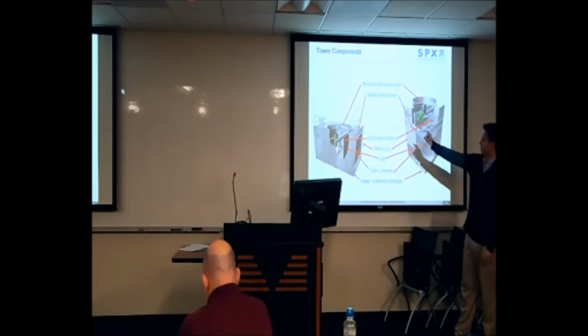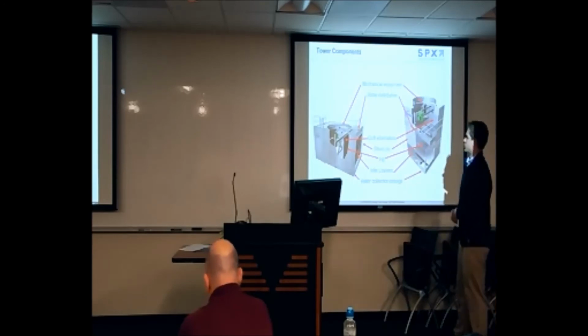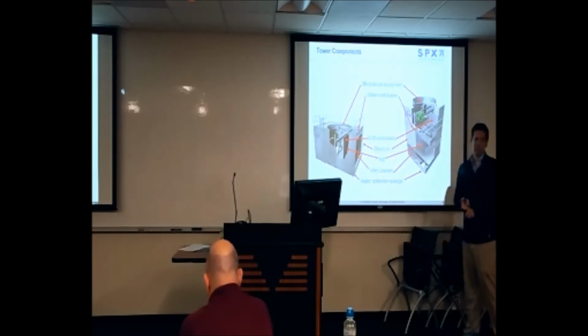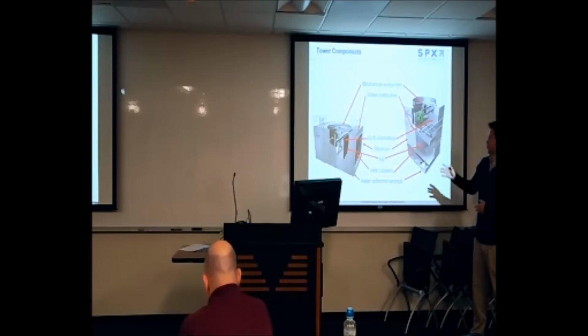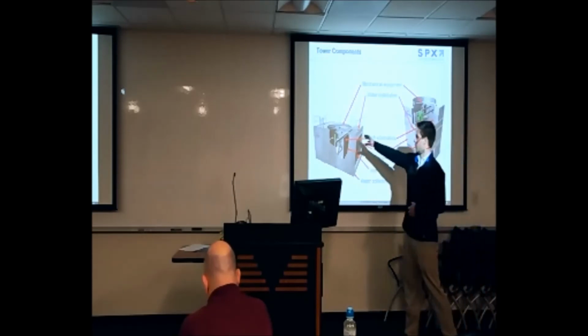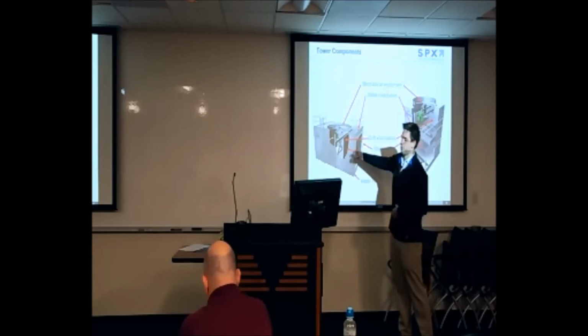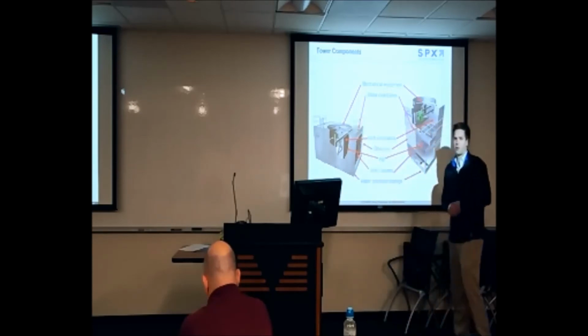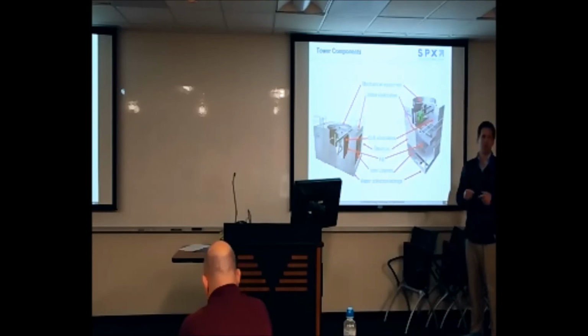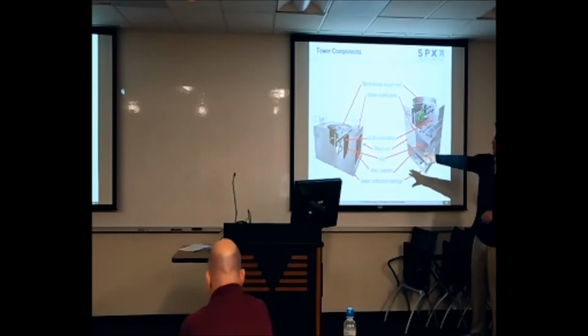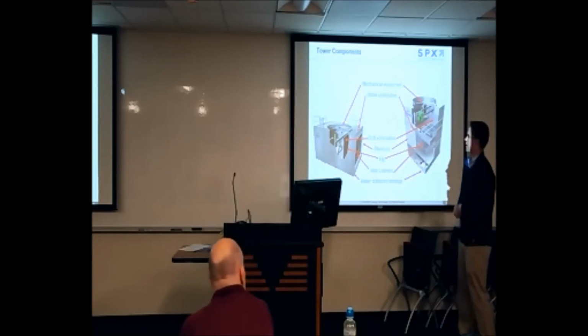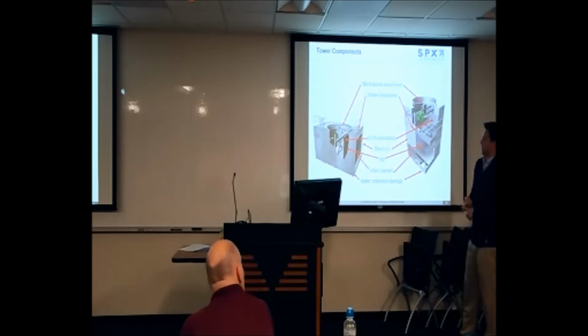So within the crossflow tower, we'll run through these components here. First off, you have mechanical equipment. Your mechanical equipment is what's going to be drawing the air. This is an induced draft fan, which means there's an axial. You actually have fan blades that are drawing air through and up out of the tower. A forced draft fan, which some of you may or may not be familiar with, has a centrifugal blower that's actually pushing air up and out of the tower. Your tower is an axial induced draft fan, just like it's pictured here on the left. With your mechanical, you have your fan, you have a gear reducer, and you have your motor. Those are your three main mechanical components, and you'll be doing maintenance on all three of those.